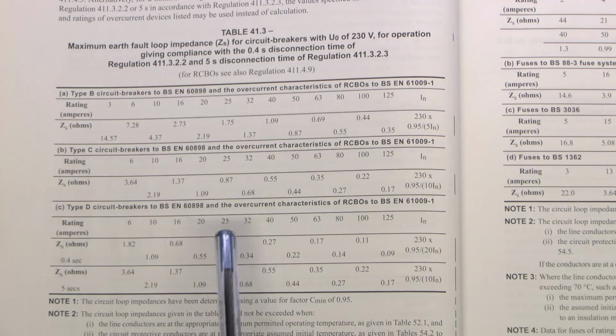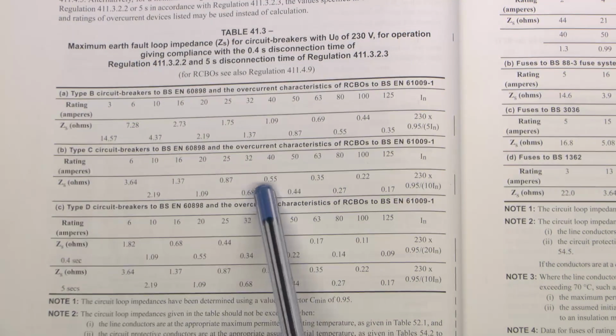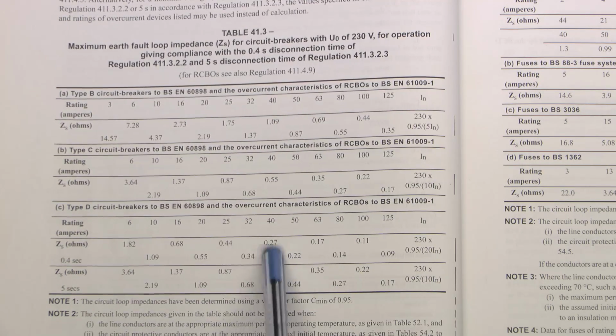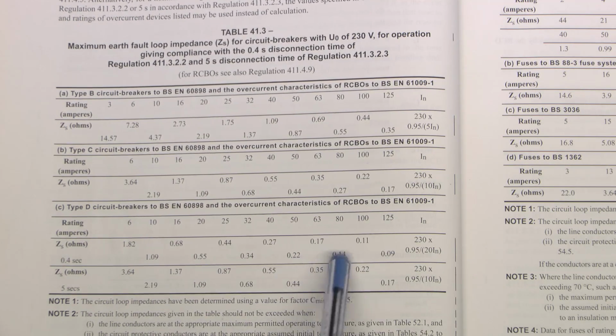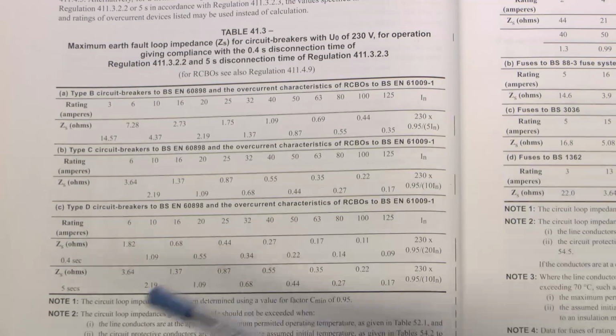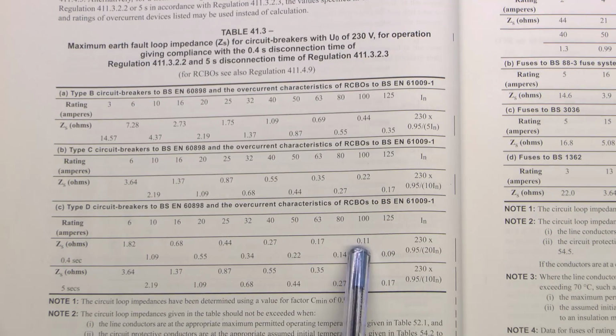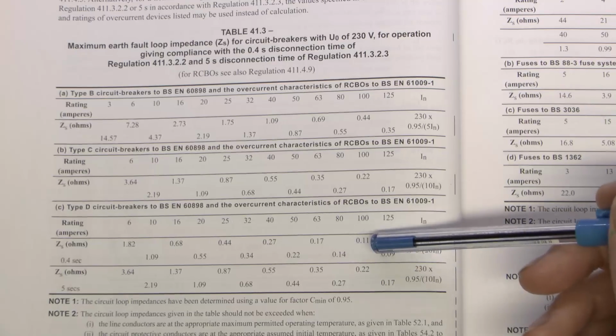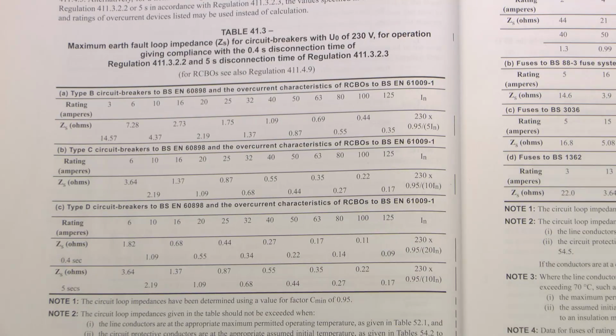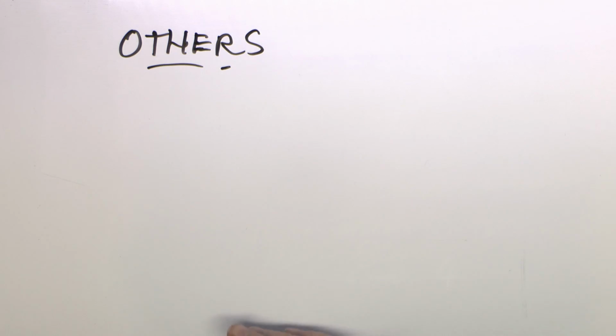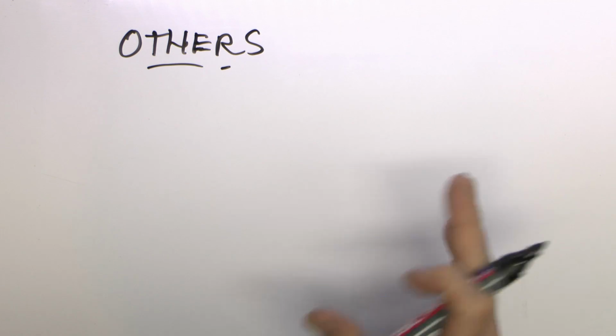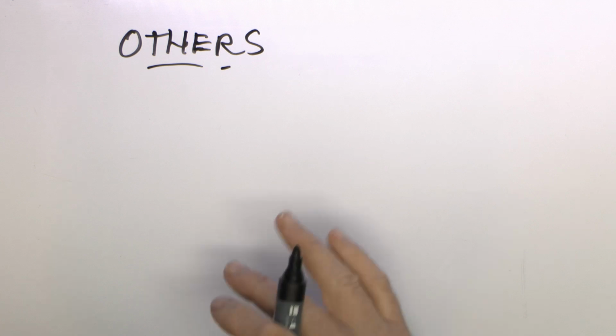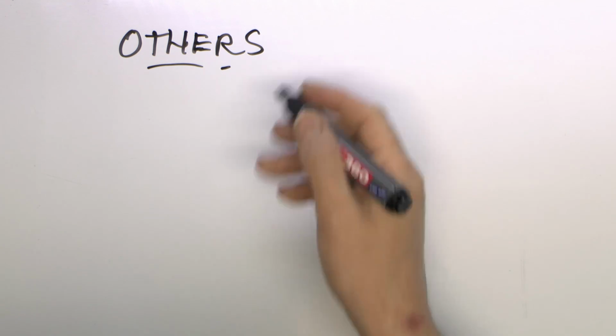And if you've already got, say, 0.6 or 0.7 at the origin, then pretty obviously fitting a Type C is not going to happen. And of course with the D it's even worse. And certainly if you get them to, say, the high rating of, say, 63 amps and above, the actual impedance you need for the whole system is incredibly low. Not something you're going to find on the majority of installations. Now there are a couple of other types which, although are available, they're fairly uncommon, but nevertheless they do exist.